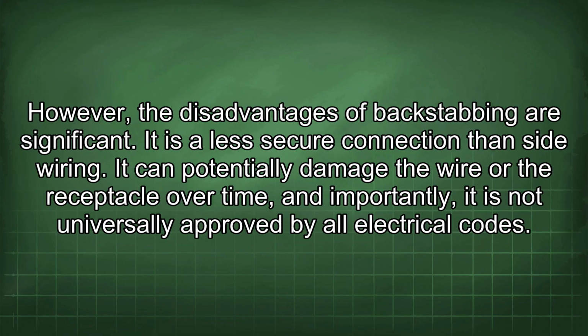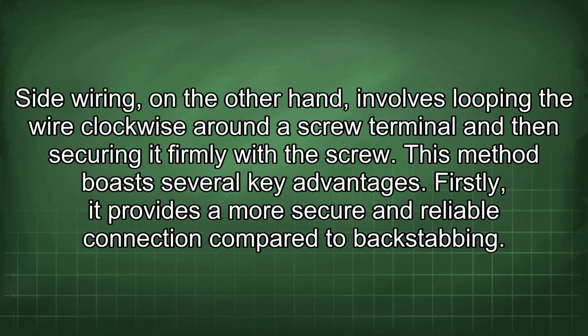However, the disadvantages of backstabbing are significant. It is a less secure connection than side wiring. It can potentially damage the wire or the receptacle over time, and importantly, it is not universally approved by all electrical codes. Side wiring, on the other hand, involves looping the wire clockwise around the screw terminal and then securing it firmly with the screw.